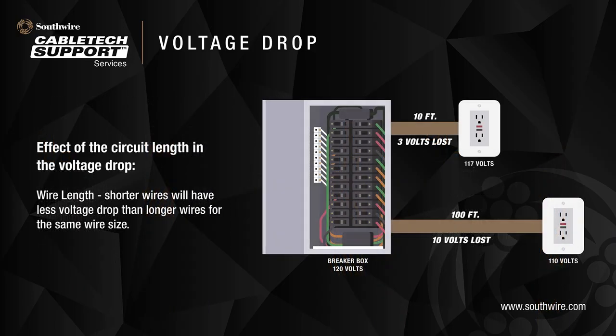The effect of circuit length on voltage drop: shorter wires will have less voltage drop than longer wires for the same wire size. For the same wire size, in a circuit length of 10 feet the voltage drop will be 3 volts, but at 100 feet of length the voltage drop will be 10 volts.